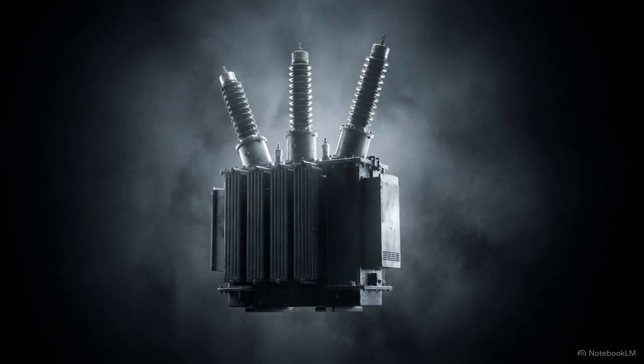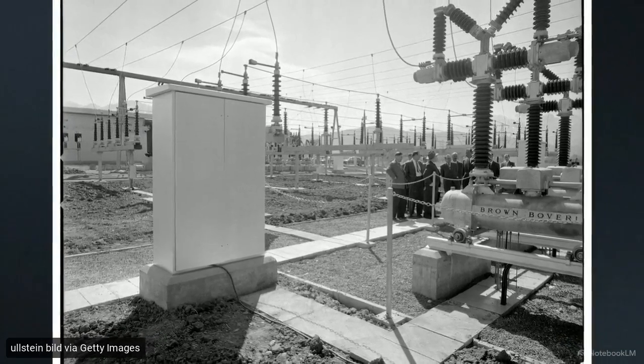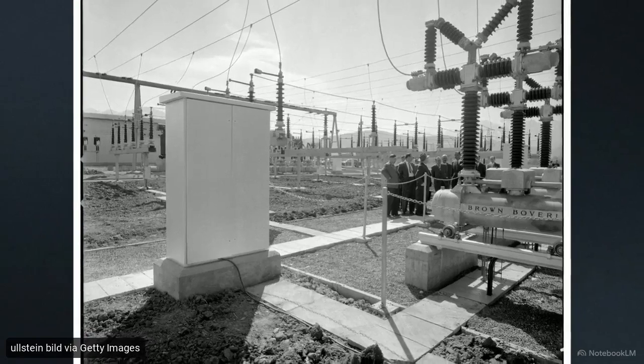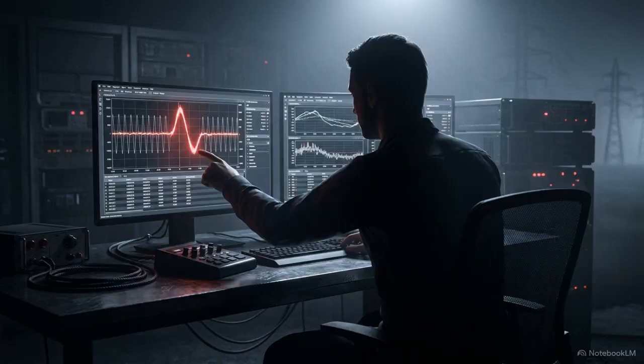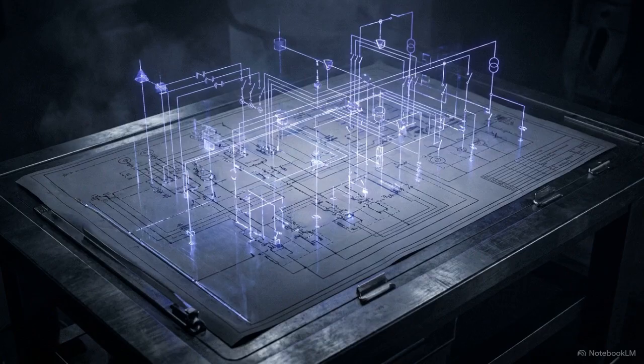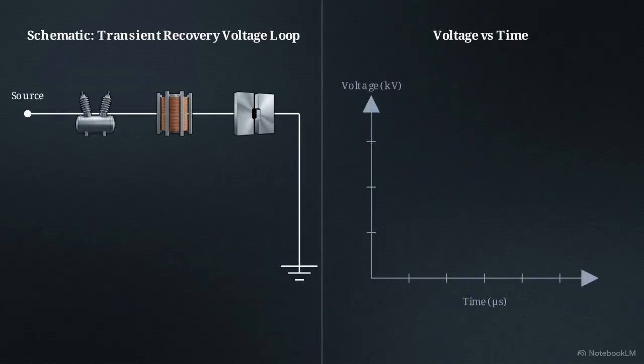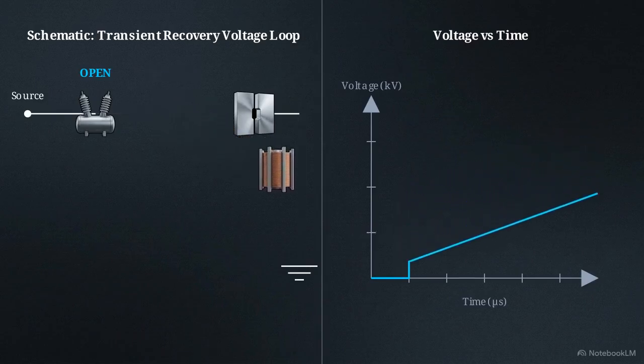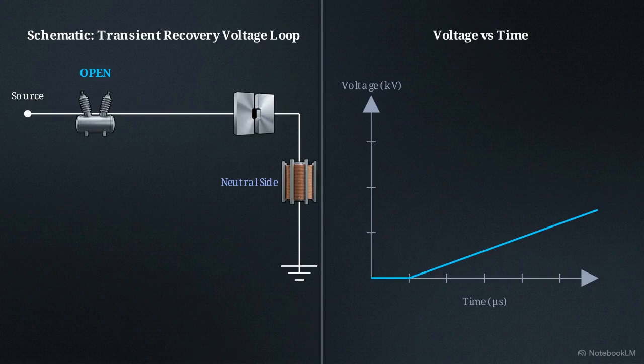A circuit breaker cannot be evaluated in a vacuum. Its ability to clear a fault is intrinsically tied to the exact physical location it occupies on the grid. When grid planners calculate a prospective TRV that exceeds a breaker's physical limits, they have to redesign the local system to alter the physics of the network. One approach is structural. Moving current-limiting reactors from the source side to the neutral side of a capacitor bank completely eliminates the initial massive step jump in recovery voltage.